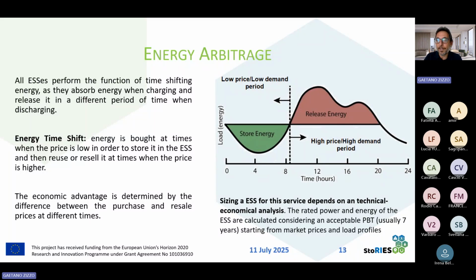We can store energy and release it later. The sizing of the batteries for this service depends on a technical and economical analysis. So the user that wants to install a system for energy arbitrage must be aware of the market prices, must be aware of the load profiles in the area, in the market area, and so must study the market results of the previous years, and then must evaluate the right size of storage to install for delivering this service with an adequate payback time. Usually for this application, a payback time of 7 years is acceptable. Over 7 years is not considered convenient.